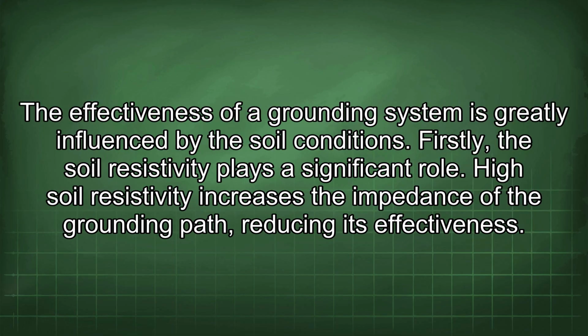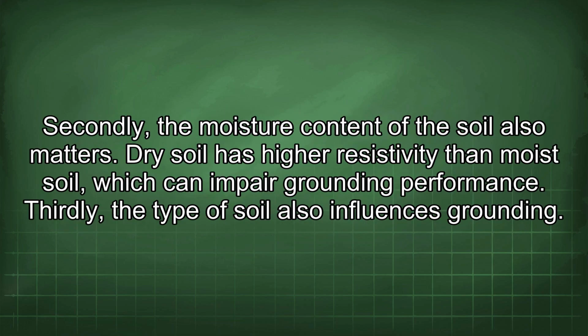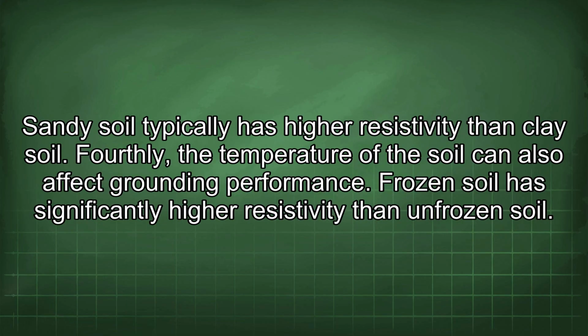The effectiveness of a grounding system is greatly influenced by the soil conditions. Firstly, the soil resistivity plays a significant role. High soil resistivity increases the impedance of the grounding path, reducing its effectiveness. Secondly, the moisture content of the soil also matters. Dry soil has higher resistivity than moist soil, which can impair grounding performance. Thirdly, the type of soil also influences grounding. Sandy soil typically has higher resistivity than clay soil.